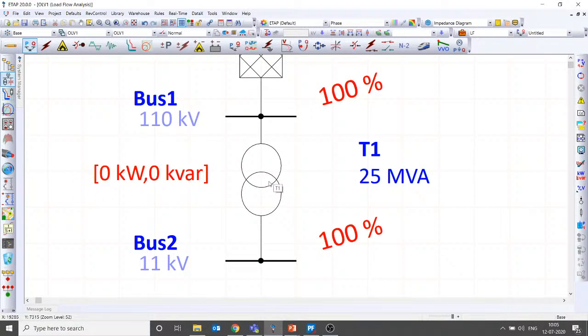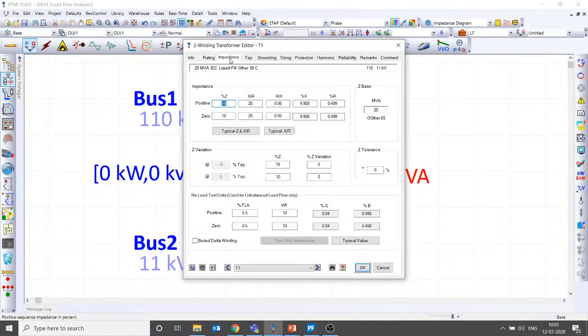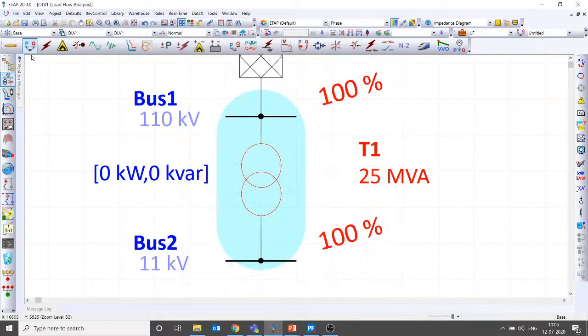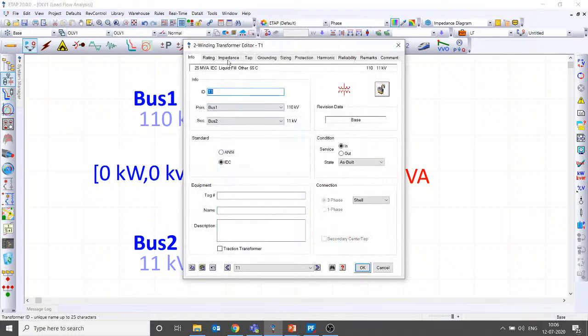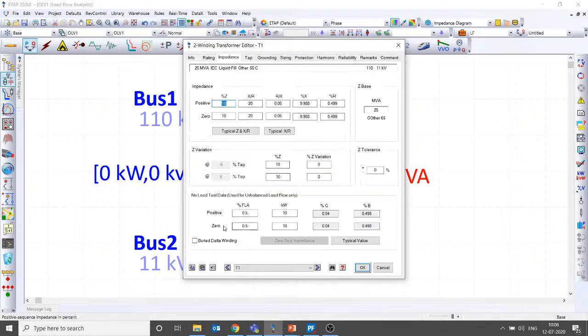The simple reason is that the software ETAP, in a balanced load flow, doesn't account for this no load loss, irrespective of whatever data you give. The load flow we are running now is a balanced load flow, and it is by default understood in ETAP to be a balanced load flow. So it will not account for the no load loss at all. If you want to account for the no load loss, the analysis you need to perform is an unbalanced load flow.